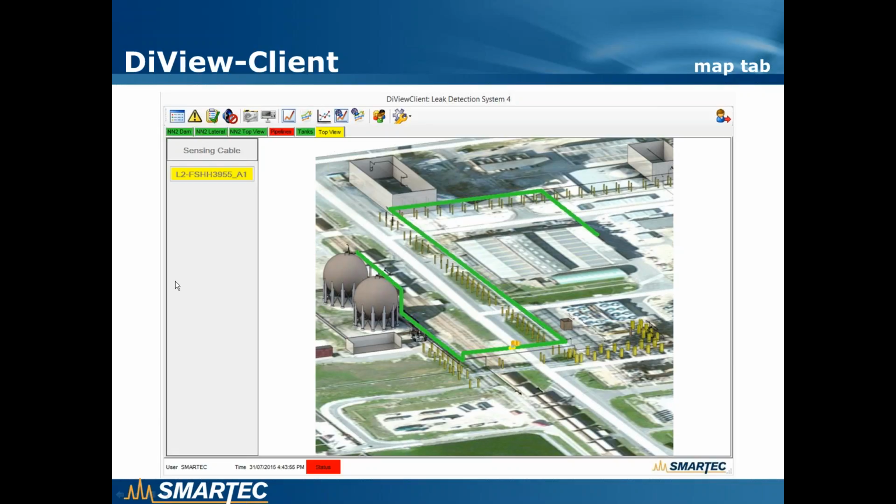In this slide, instead, there is another visualization in which we have the map with a yellow flag. This indicates that there is a point waiting for the stop, for which the user had already done the acknowledge. You see there are different colors of the tab. So there is the green tab, it means that all is working properly. Red tab, it means that there is an alarm in progress. And the yellow tab, it means that there is an alarm already acknowledged but waiting for the stop.